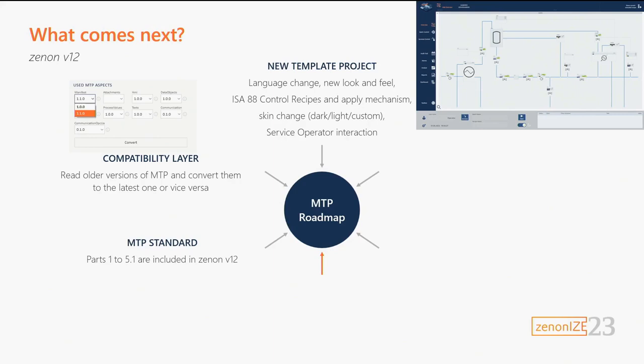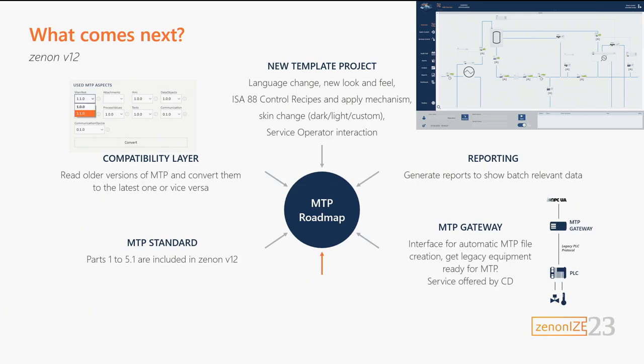Let me focus on one important topic: legacy equipment. You have equipment already but you don't want to throw it away just because of MTP. The solution is the MTP gateway — think of an adapter. You put this adapter on top, leave your equipment as it is. The equipment can have its own software developed over the last 30 years. The gateway includes all the MTP logic, the MTP status model, OPC UA, and the tag structure. You can even use a skid with just IOs, and the MTP gateway provides the logic to make the device intelligent so you can orchestrate it via MTP.